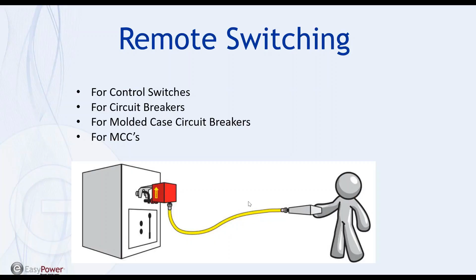To walk through some examples, you'll see that what we're looking at here is one of the traditional Chicken Switch devices, mounted on a pistol grip control switch. There are about 6 different models for different sizes of control switches. Keep in mind, these control switches are often mounted right above a breaker, a lot of times a medium voltage breaker or something high like that, and the need to get away from it is paramount. That's what this solution provides.